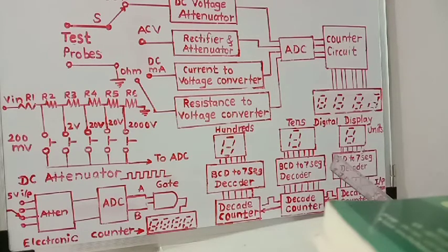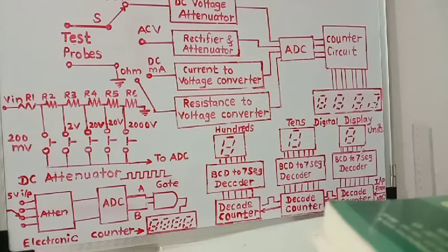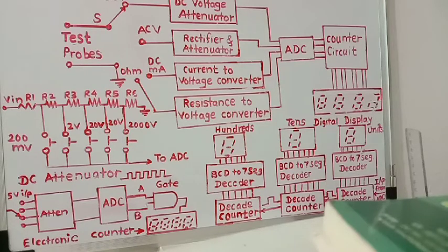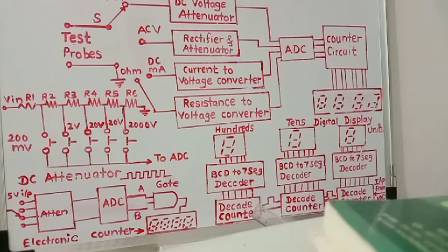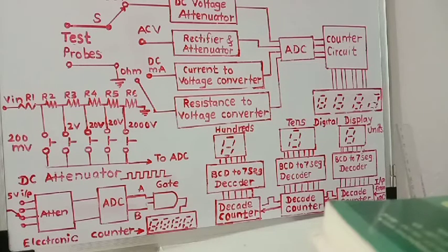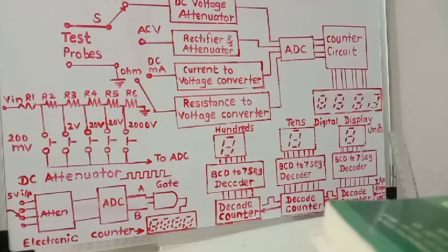For resistance to voltage measurement, the unknown resistance is connected in an op-amp circuit through which a constant current is passed. This constant current is passed through the unknown resistance, producing a voltage drop across it, and this voltage drop is then measured by the usual digital method.